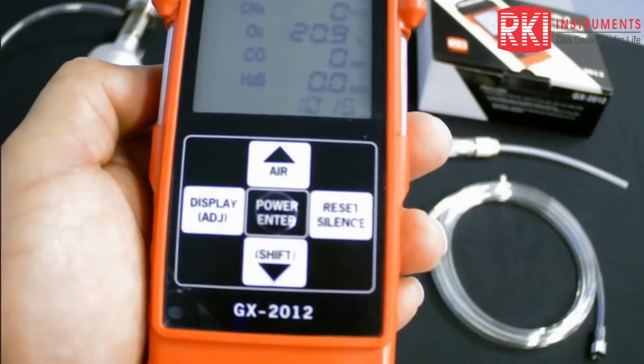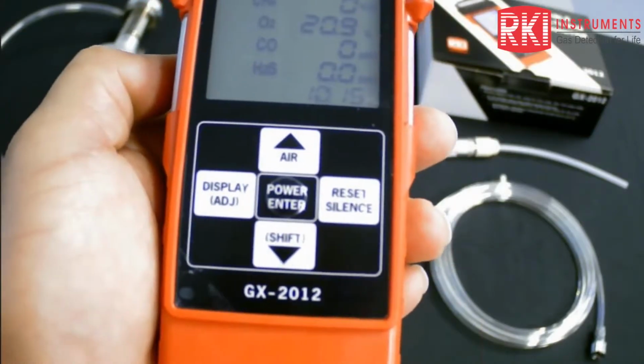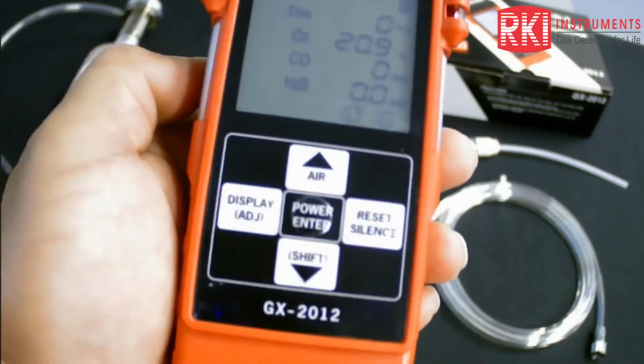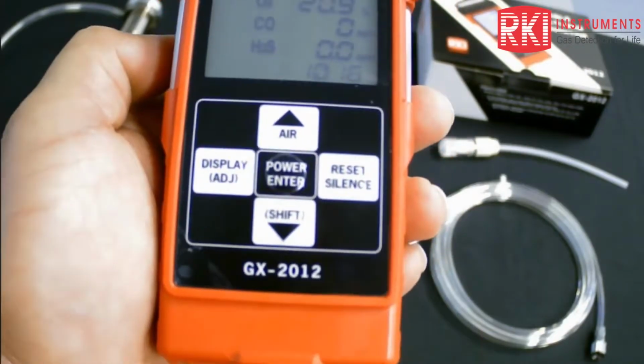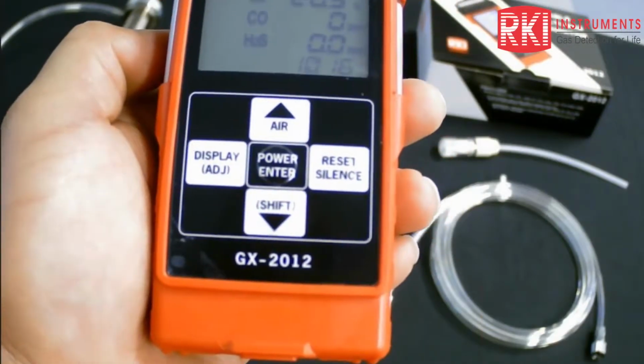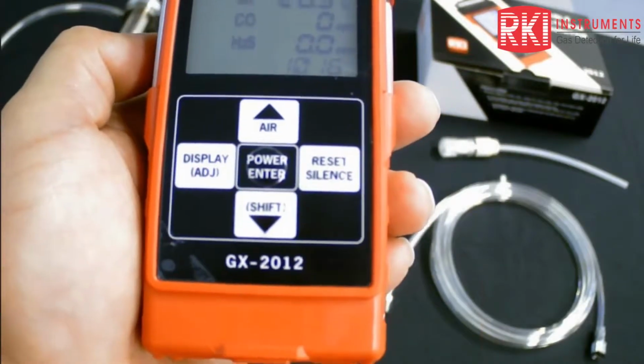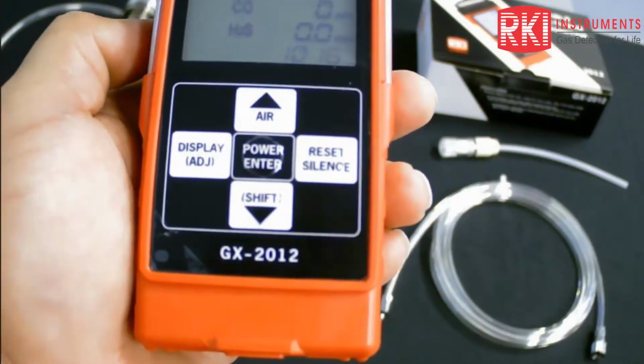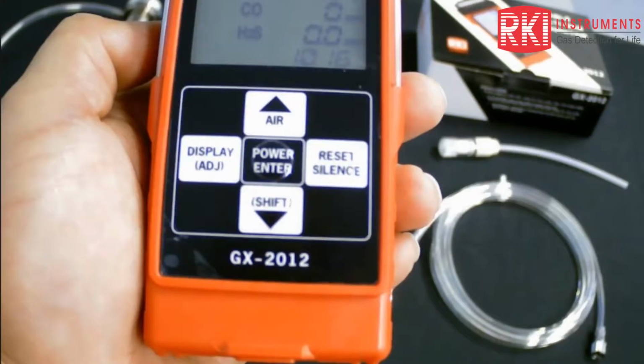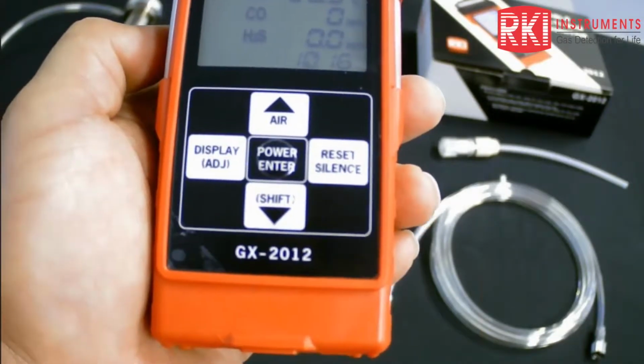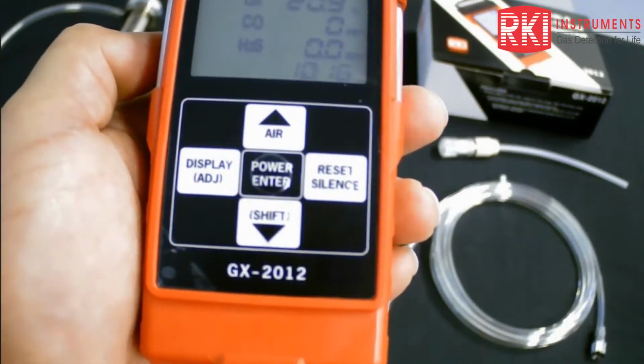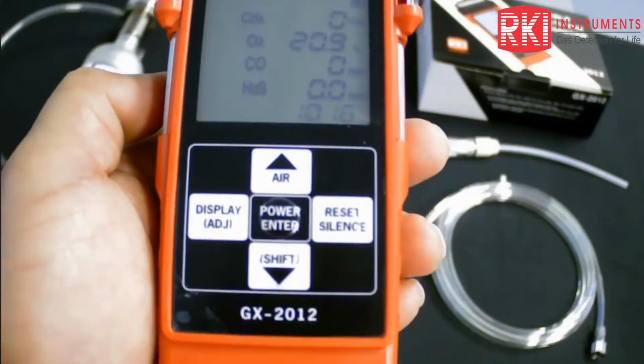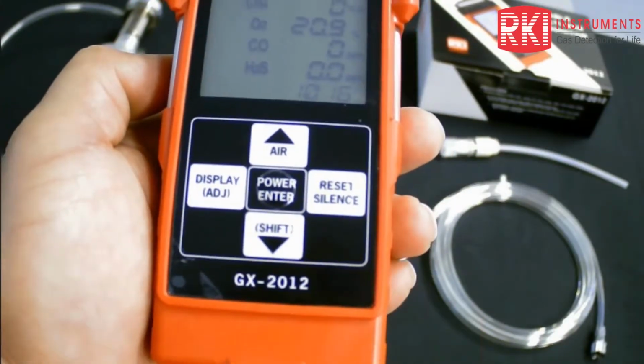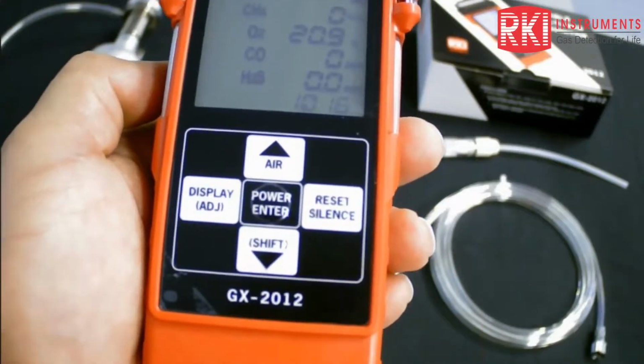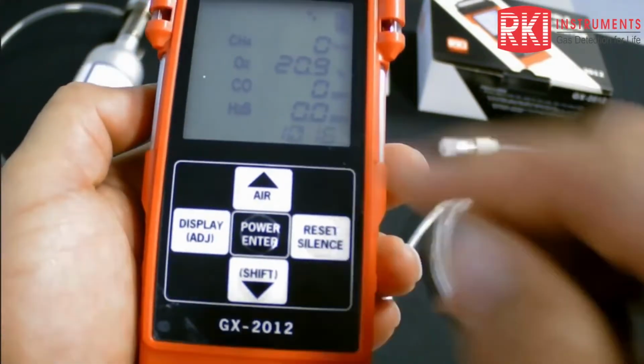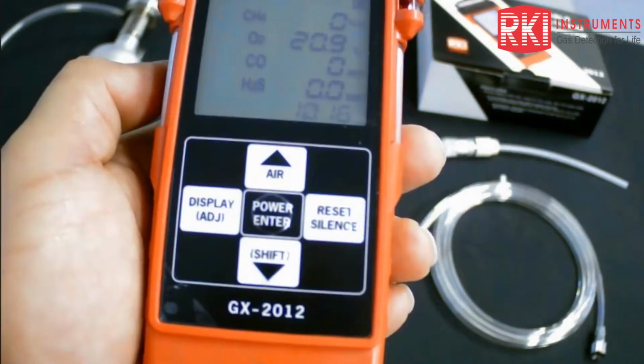But as a result of just cooling it, we don't have a catalytic coating on it. So therefore, it's not going to prematurely have a short life with a lot of exposure to gas. It doesn't need oxygen to operate, whereas the catalytic does. Since we are oxidizing the gas on those heated elements, we need oxygen to get a reading. We need about 8 to 10% volume of oxygen to get an accurate reading on that catalytic sensor. So basically, those are the technologies as they apply to these sensors.